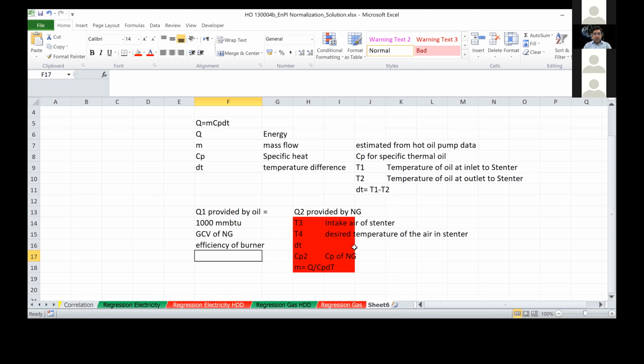For example, let's say 1000 MMBTU of natural gas is required, and the burner is 60% efficient. So 1000 divided by 0.6 means we need 1,666 MMBTU of natural gas. This amount in MMBTU can be converted into cubic meters and then converted into the cost of natural gas.